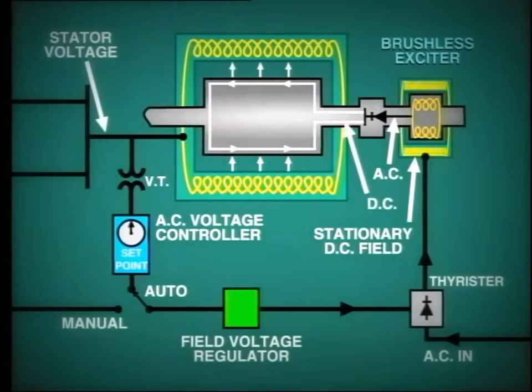The DC output from the rectifier is connected directly to the main rotor winding through leads which pass inside the shaft. There is no need for collector rings or brushes.